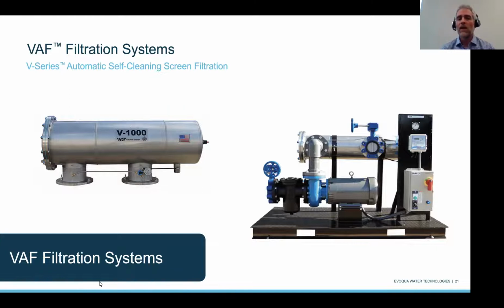Again, this product works on its own internal water pressure. So filtration is very basic. It's a very simple operation, but this technology is really differentiated by how it cleans itself. And it cleans itself by utilizing its own internal water pressure. No additional accessories, no electric motors, no pistons, no hydraulic systems are required to operate the cleaning system. Again, it's fully automated, working on a DP controller that cleans itself throughout its operation. And the product comes in various different sizes, models, and configurations, from 200 GPM all the way up to about 3,500 GPM, depending upon your solution. It comes both in a skidded operation as well as non-skidded.